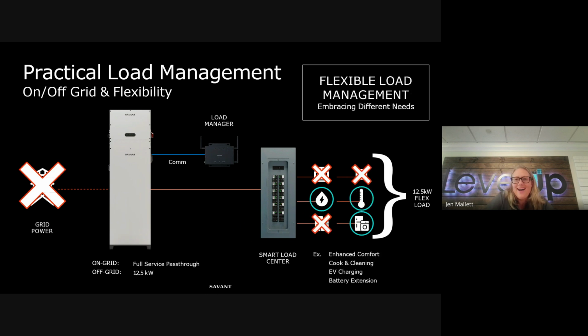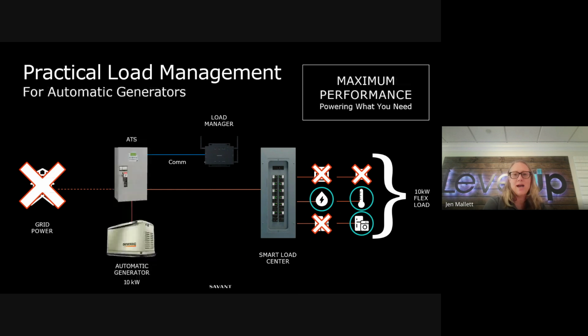Flexible load management is another version of embracing different needs. For a smart load center, we can have enhanced comfort, cooking and cleaning, EV charging, and battery extension. So in this scenario, instead of all-or-nothing load management, flexible load management means that if we've got 12.5 kilowatts of flex load, this homeowner can prioritize what's most important to them, whether that's comfort, cooking, cleaning, EV charging, and battery extension, or the opposite. The ability to have that flexibility is really created through this design and the smart load center.